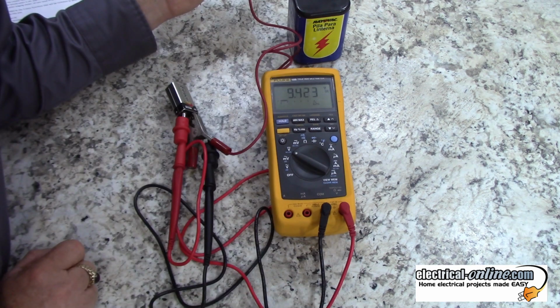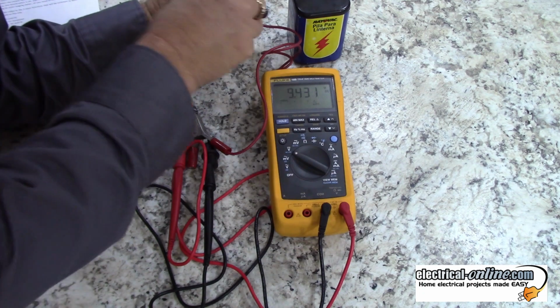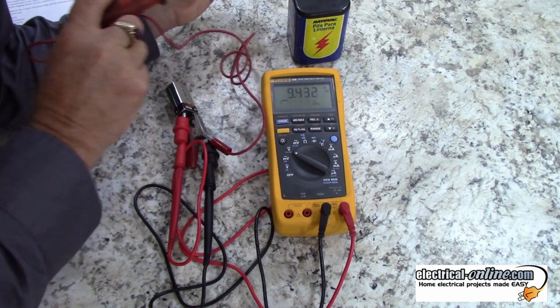As a side note, when testing batteries to check for voltage, open circuit voltage doesn't necessarily mean the battery is good, because you need to put a load on it. Let's demonstrate that.